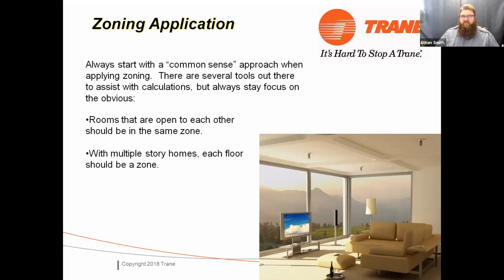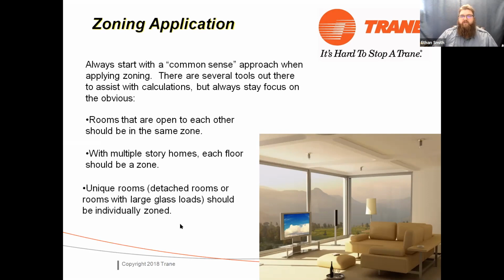With multi-story zones, each floor should be a zone or multiple zones. We start talking about thermoclines in a house, and temperature graduations in a house. Further up in the house you get, heat rises, guys, cooling falls. So we want to zone off our different floors. Okay. Unique rooms like detached rooms or rooms with large loads. We see this a lot down in New Mexico, where we'll have large rooms with giant glass vistas opened out to the south face of the valley or something like that. Somebody wants to look at the view. It's great. You got all that glass to look out.